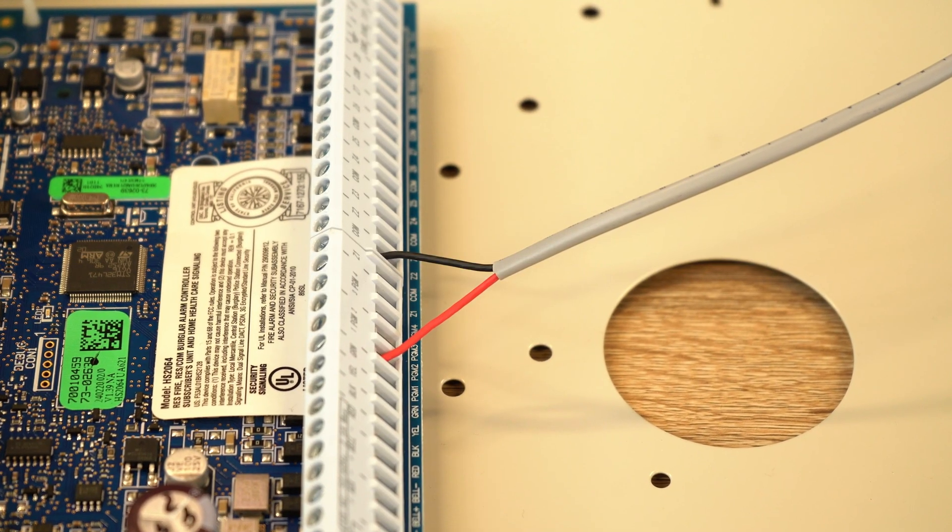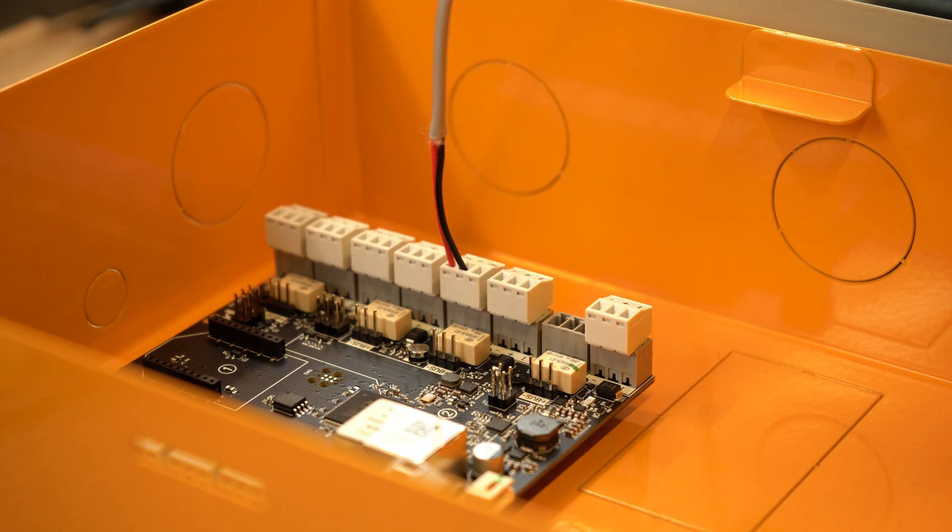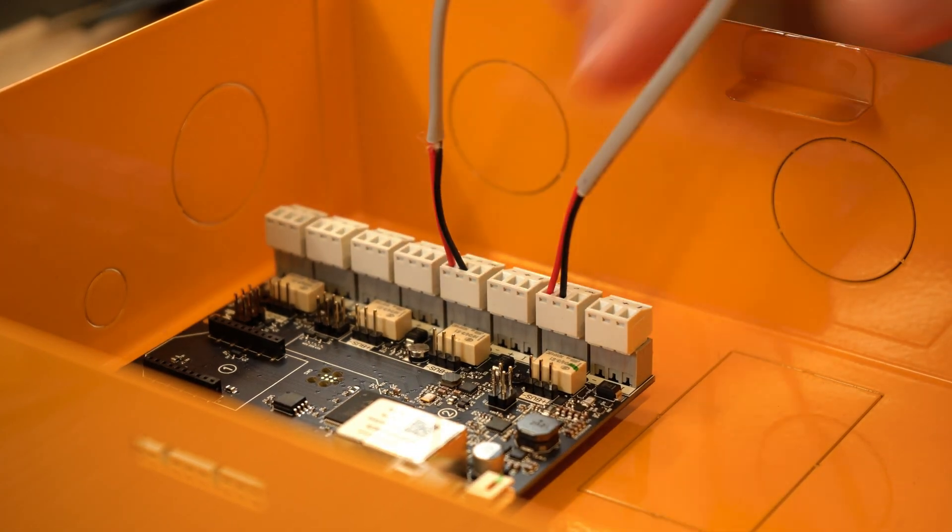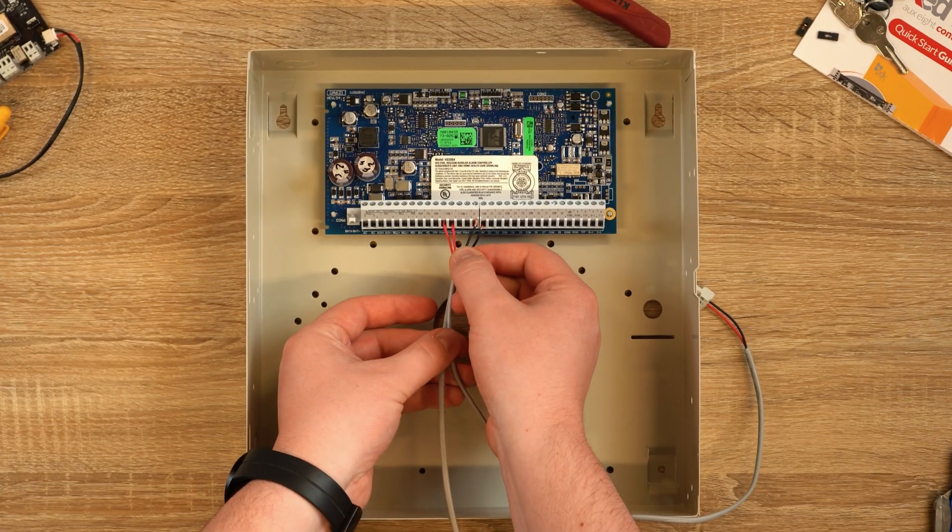Likewise, if there is an arm option on the alarm panel, take another two pair of wire and do the same. Common of PDK panel to common of the alarm panel, normally open of PDK panel to arm of alarm panel.